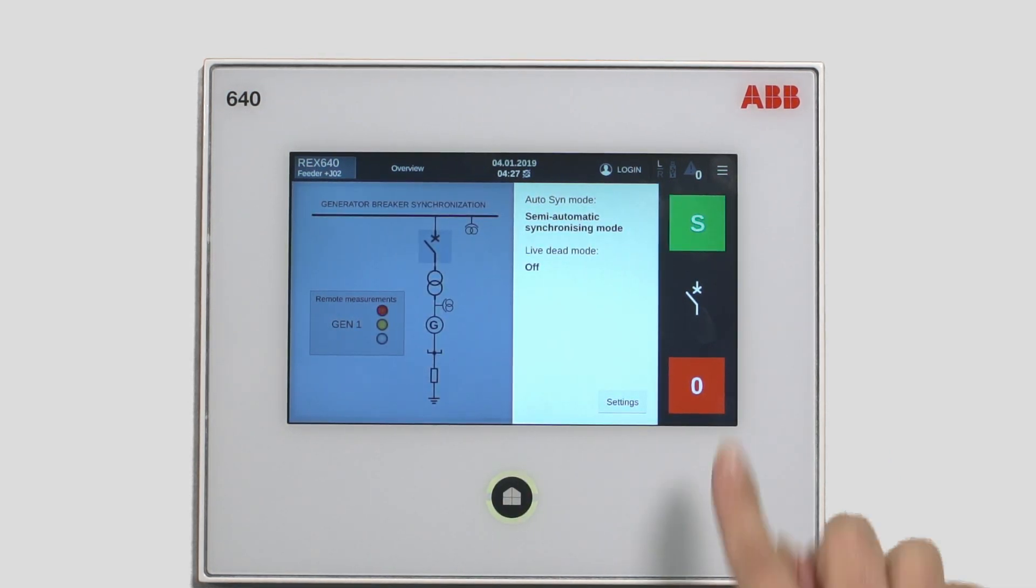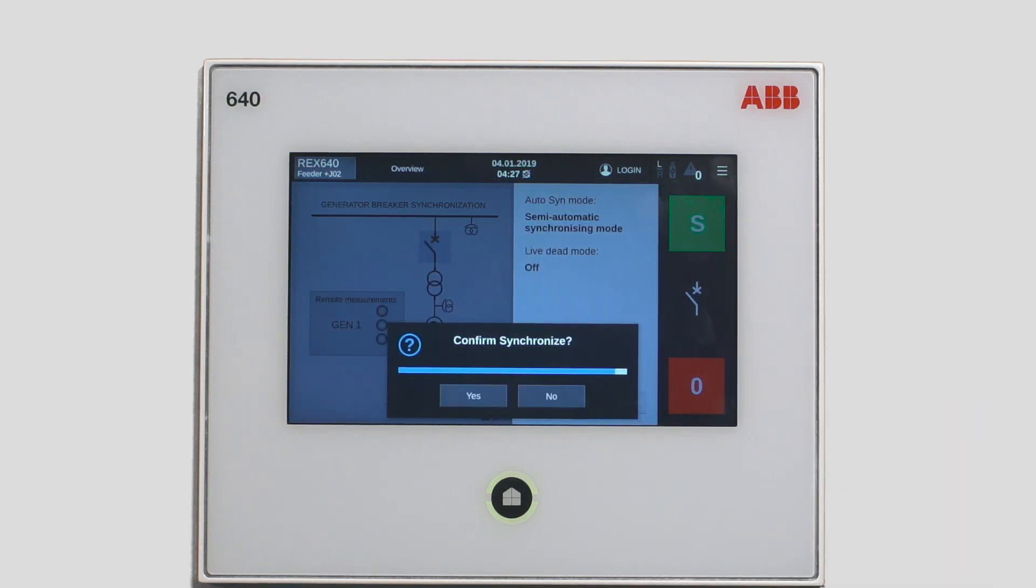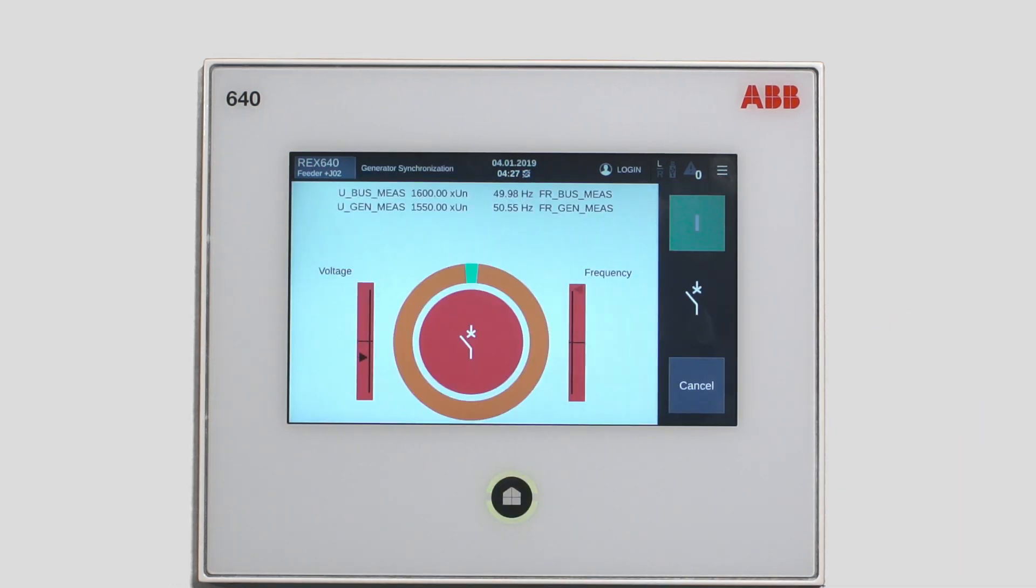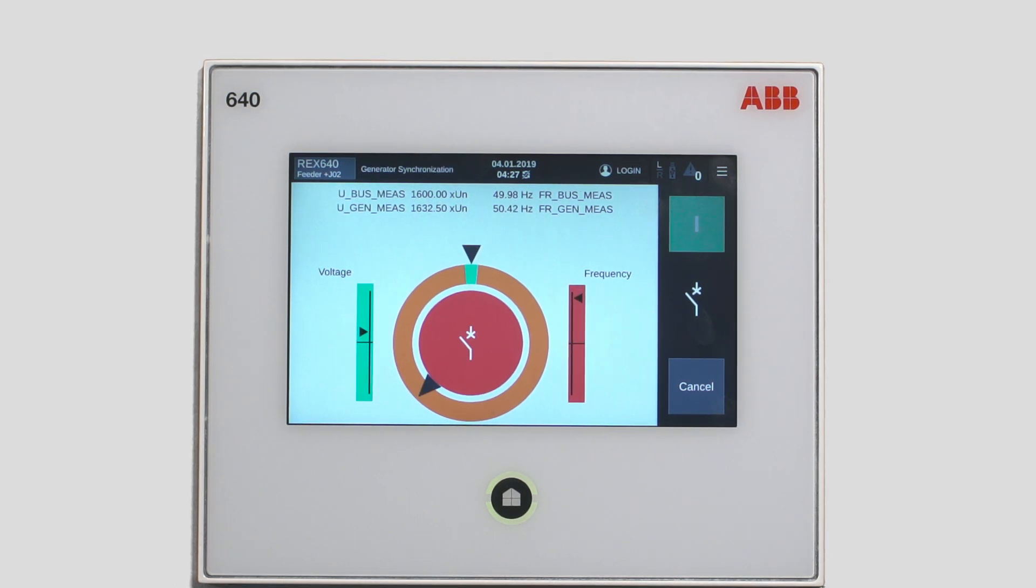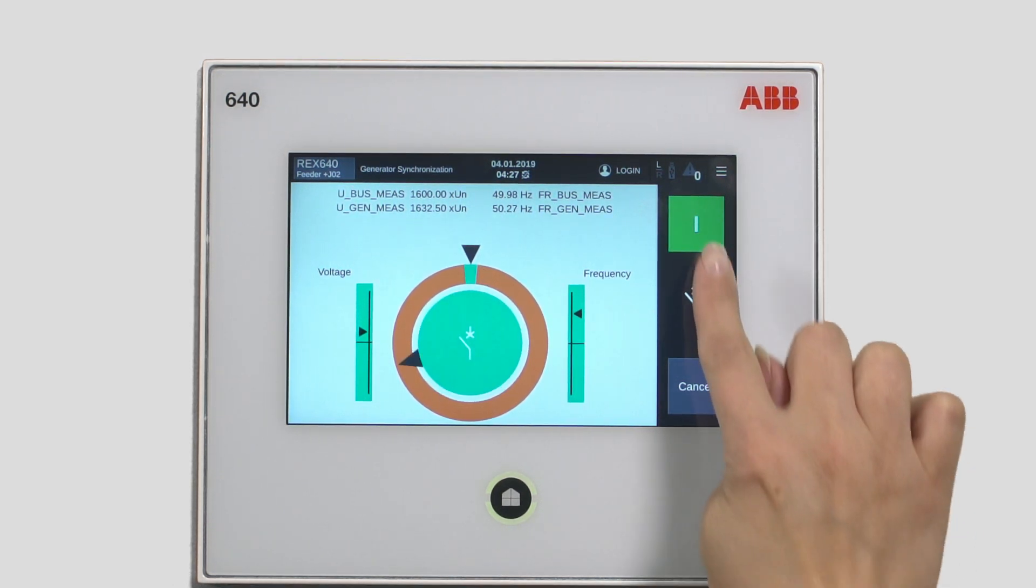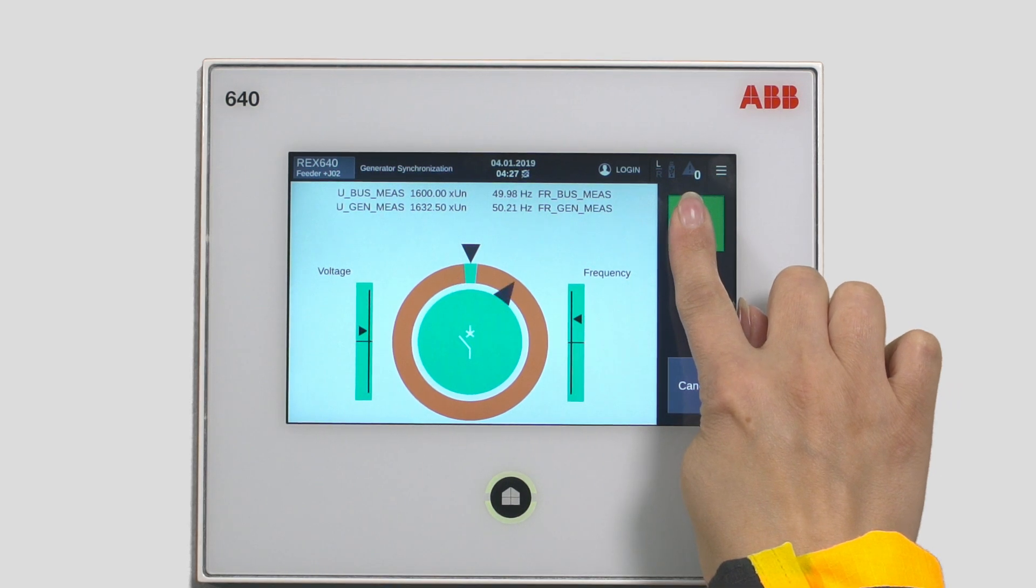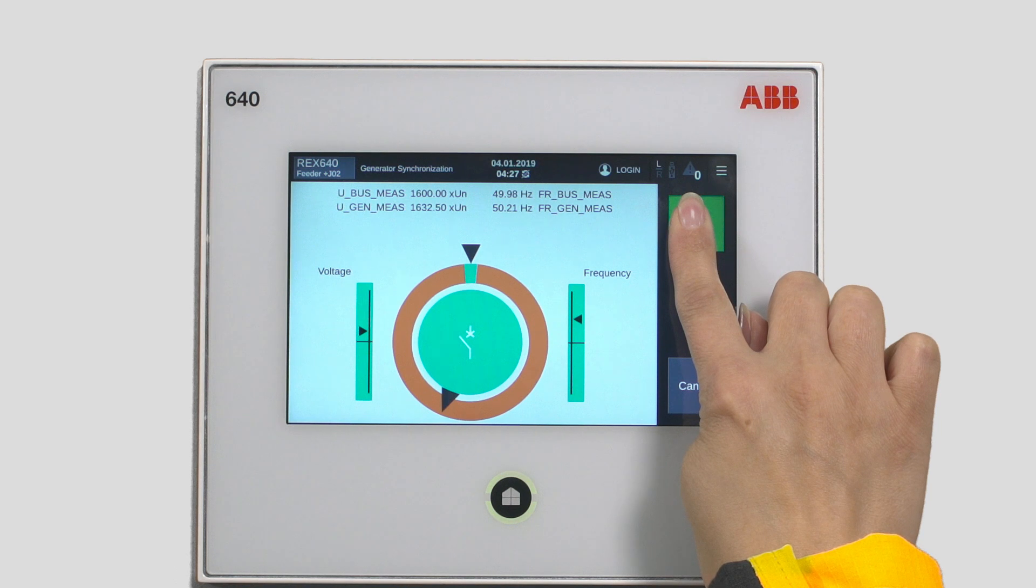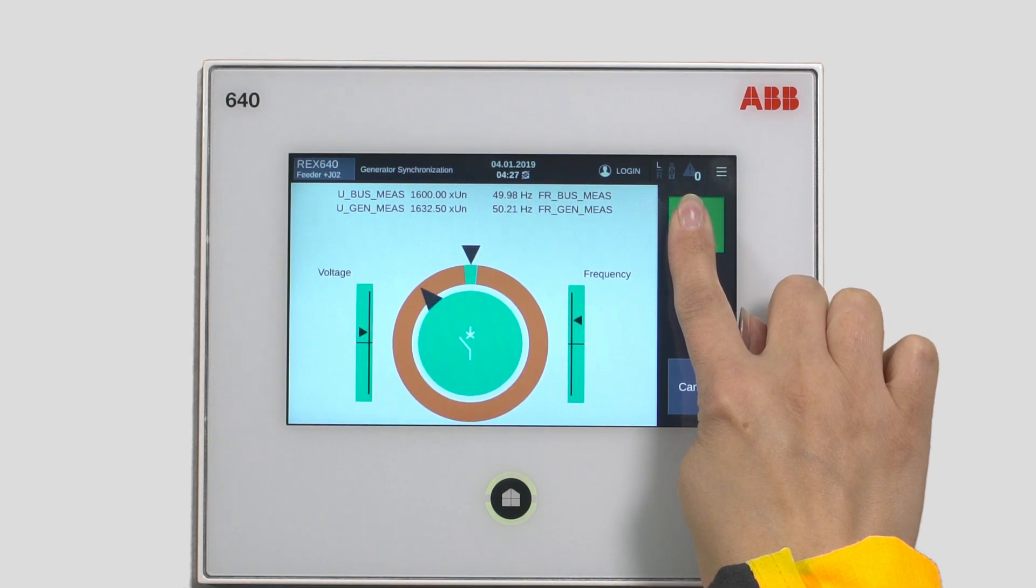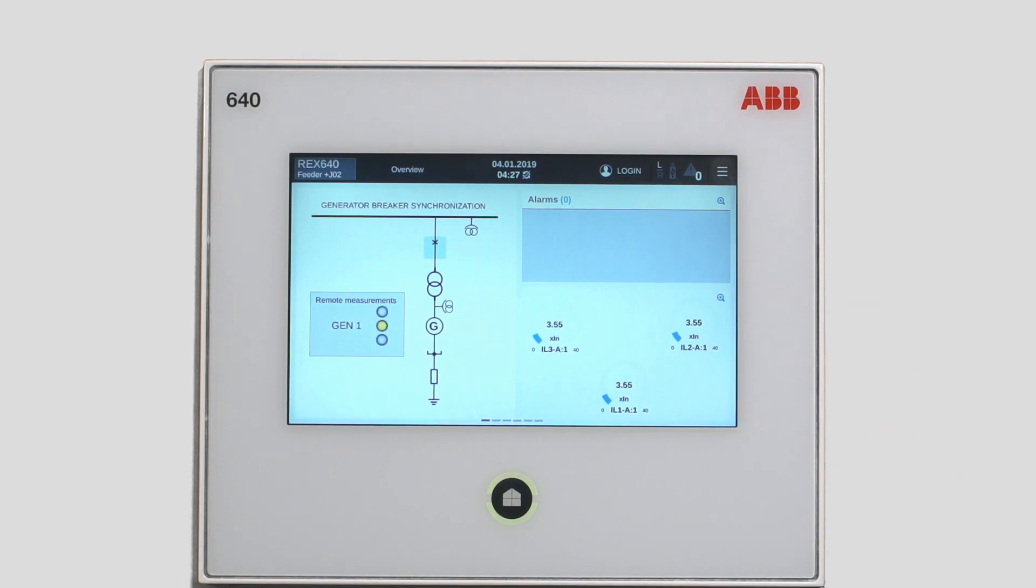Once the green S is illuminated, you can proceed by tapping it. The relay automatically adjusts the voltage and frequency of the generator. The green color indicates that you are within the set limits and you can start closing the breaker. Tap and hold the close button. The breaker closes as you can see now from the single line diagram.